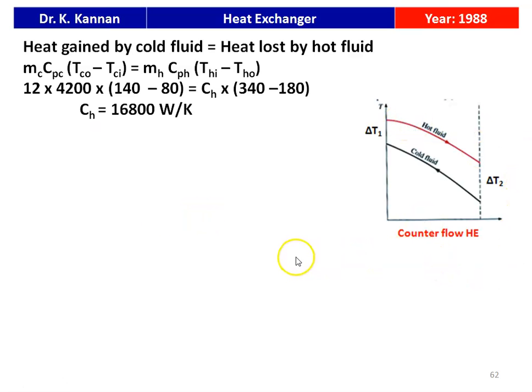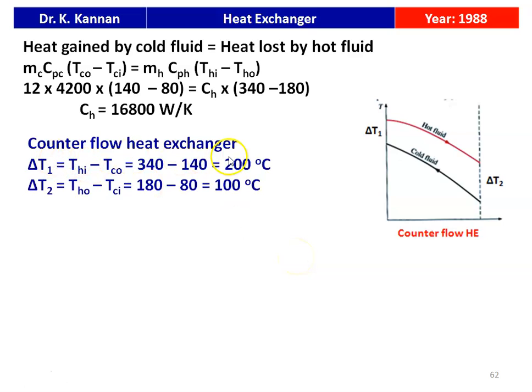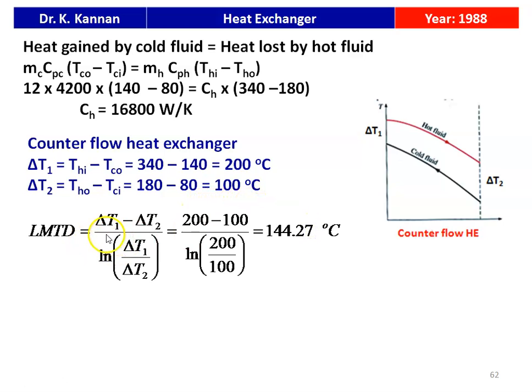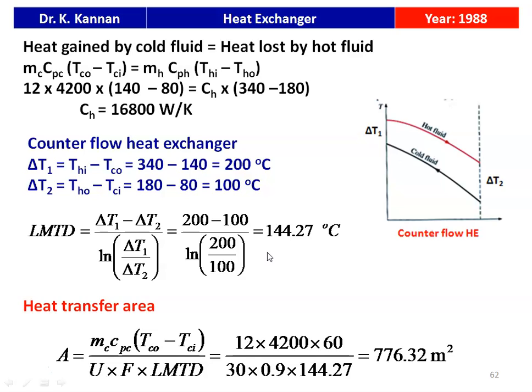For the counter flow heat exchanger temperature profile, ΔT1 = THI − TCO = 340 − 140 = 200°C. LMTD = (ΔT1 − ΔT2) / ln(ΔT1/ΔT2) = 144.27°C. Heat transfer area A = MC × CpC × (TCO − TCI) / (U × F × LMTD) = 12 × 4200 × 60 / (30 × 0.9 × 144.27) = 776.32 m².